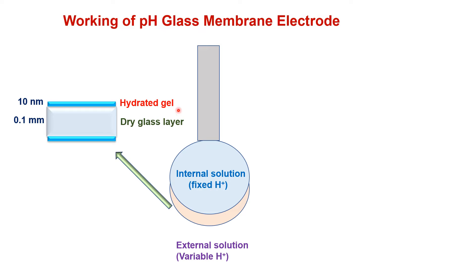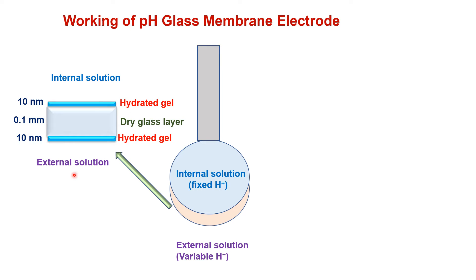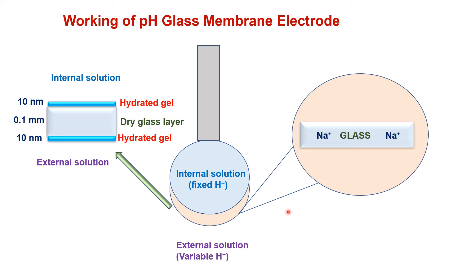The second part is the hydrated gel layer, with thickness 10 nm, which is in direct contact with the internal solution. The third part is another hydrated gel layer, also 10 nm thick, in direct contact with the external solution. The hydrated gel has exchangeable sites available for sodium ions or hydrogen ions, while the dry glass layer has fixed sodium ions. In the cross-sectional area of the glass membrane, the dry glass layer has fixed sodium ions, while the negatively charged oxygen atoms can bind cations of suitable size.